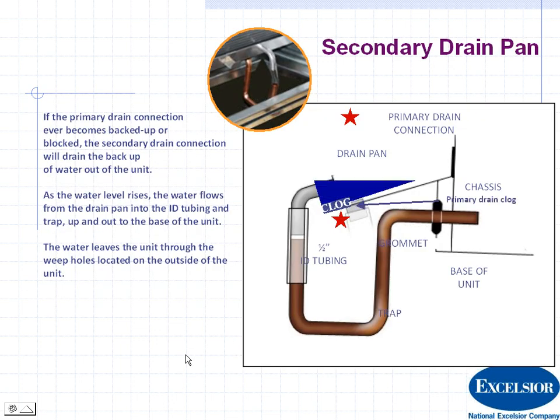And you can see that here. You can see that the secondary drain is a little bit above where the primary drain is, and that will, if there is a clog from dust or dirt or whatever in the primary drain, as the water rises, it goes out to the secondary drain, and then that goes out to the base of the unit, and that base of the unit goes out to the outside.